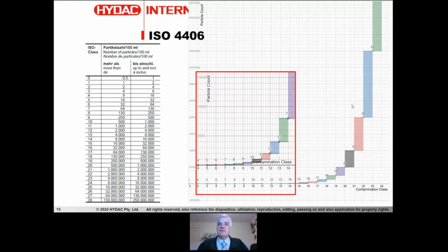Okay. So that's ISO 4406. Now, ultimately, it's the most common one for two reasons, according to me. Number one is it's ISO, it's international. So this is used equally in Europe and in North America, and of course the rest of the world. Number two is it's the easiest to apply, because it doesn't matter what size particle you're evaluating, you use the same chart. There's only one range that's used across the particle sizes being evaluated. So from that perspective, it's easier to use.